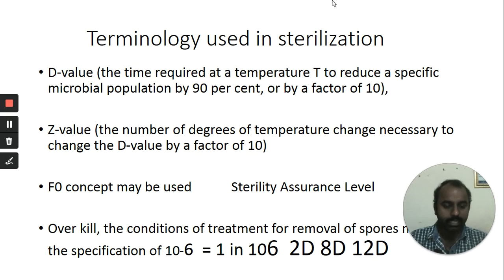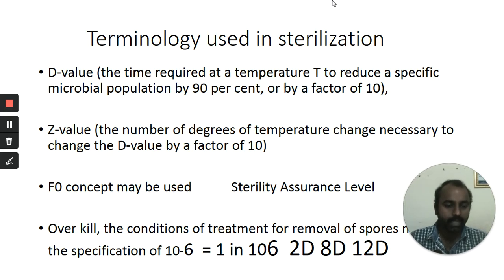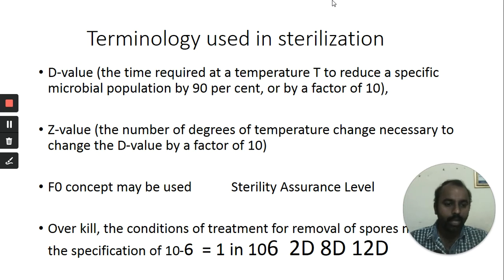In dry heat sterilization using a hot air oven, the standard protocol is 160°C for two hours. If you change the temperature — either decreasing or increasing — the modified protocol should provide the same lethality as the standard protocol. This equivalent degree of lethality is expressed in terms of the F0 concept. Sterility assurance level (SAL) tells us how well products are sterile or non-sterile.